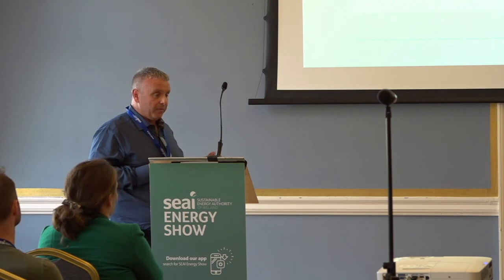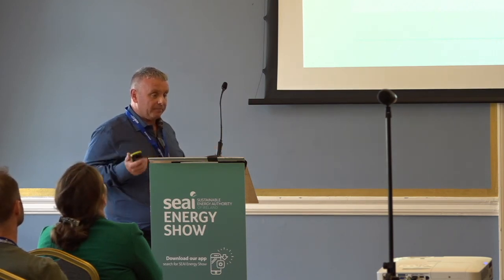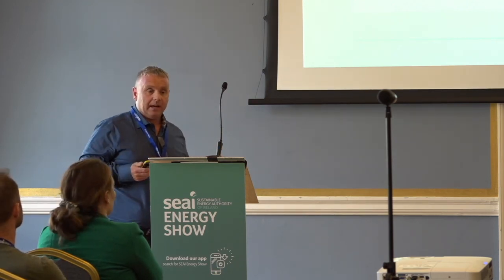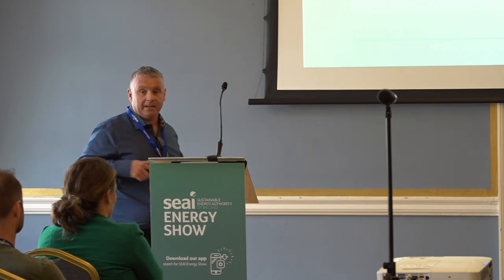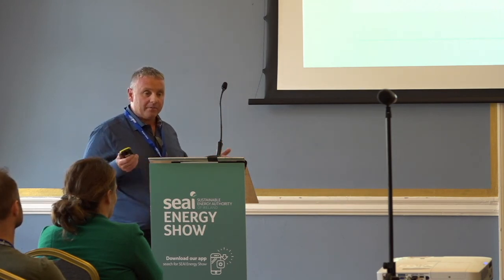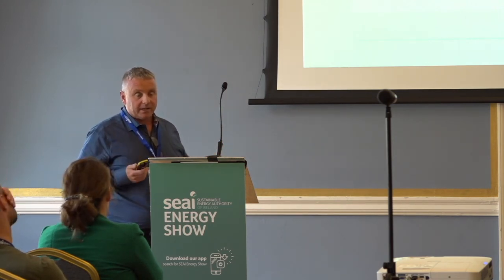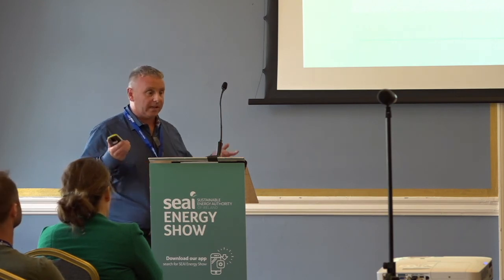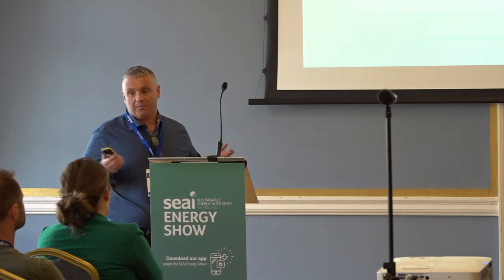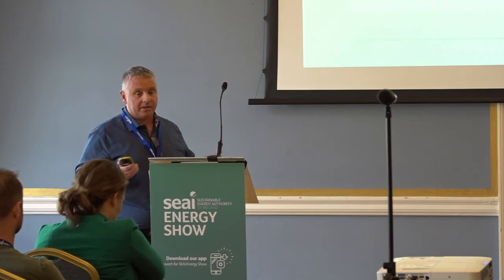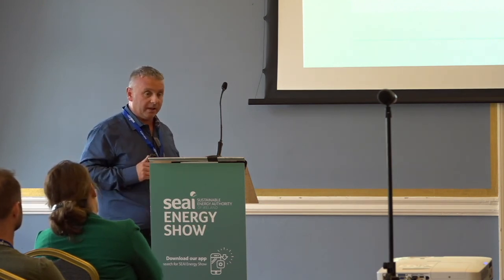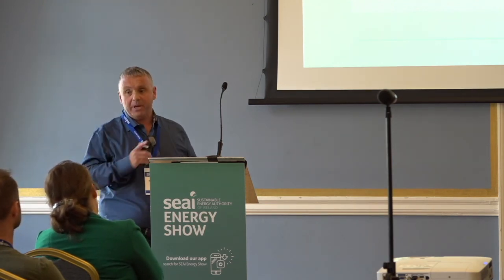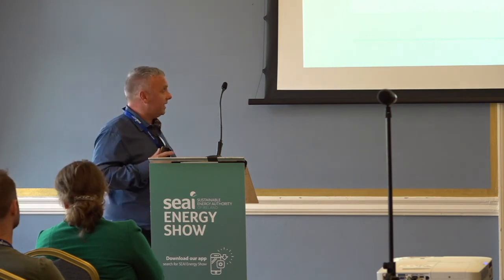Take an example: we have a room here that can hold 10 to 100 people, and it's on the BMS system. Typically in a normal BMS system, this would just be set to 21 degrees and we hope for the best. 10 people walk in, it's not an issue. 15 people, not an issue. 100 people walk in, immediately it's an issue - we have this massive heat gain and we don't account for it.